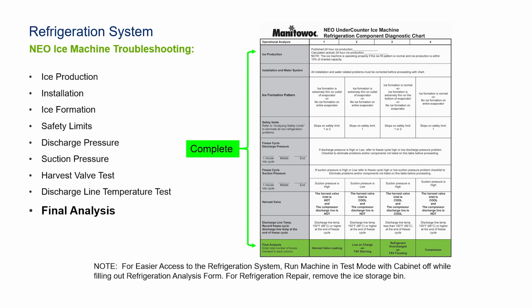But if you've been watching this ice machine for more time than it's supposed to take, let's say your freeze cycle is supposed to be 15 minutes and you're at 25 and you don't have a lick of ice. Everybody, I would just turn that machine off at that point, get the gauges, put them on, turn the ice machine back on, and then go through this flow chart. If you answer every question accurately, you put your checks where they are, there is no way to get a tie. So we're not going to go through the full bit here. Also, again, to have easier access to that refrigeration system, you could run this test with the bin off in the test mode, utilizing the test button on the control board.